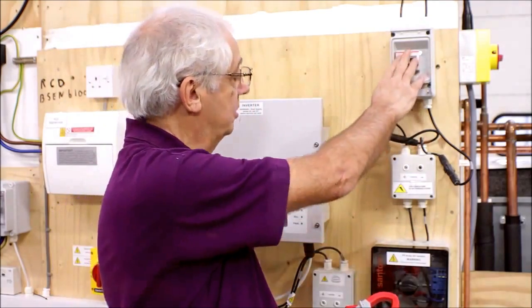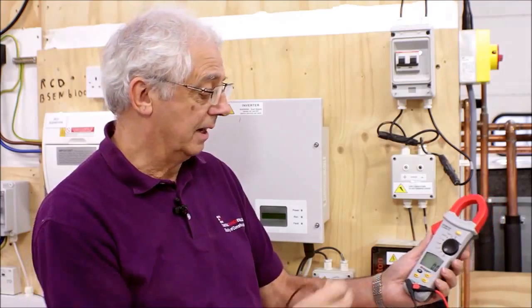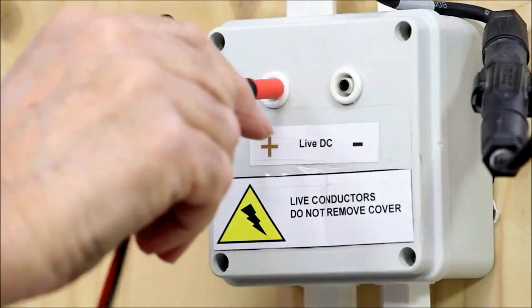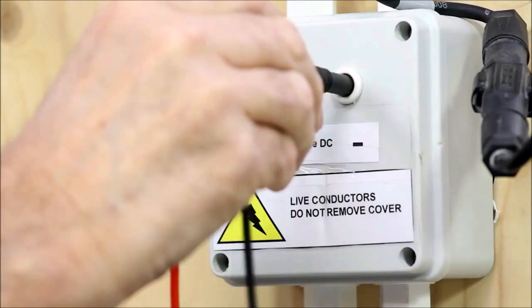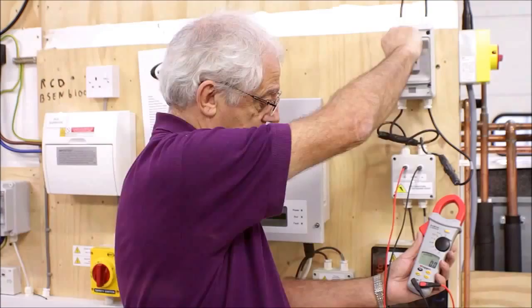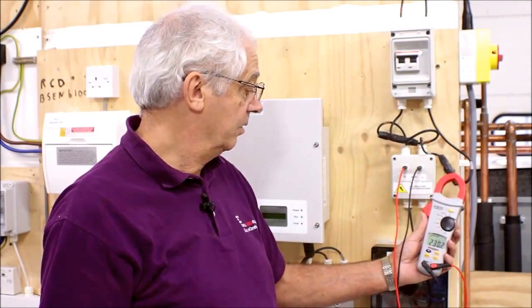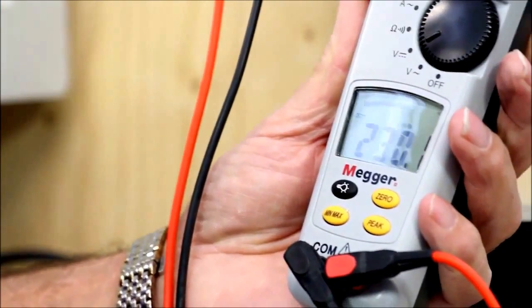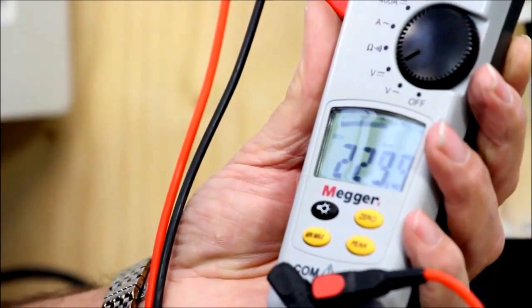So what I need to do is turn this off. I'm going to use my clamp meter set to DC voltage. Switch it back on. And I've got a value of 230.1, which is really, that's as close as I'd expect it to be. And that's telling me that the system is working as well as it should be. In this country, the sort of weather conditions we get, the effect of temperature against voltage is very, very small, to be honest, so it's not really worth considering.